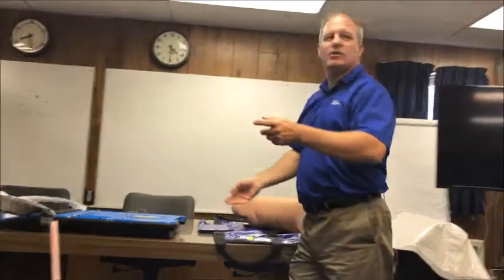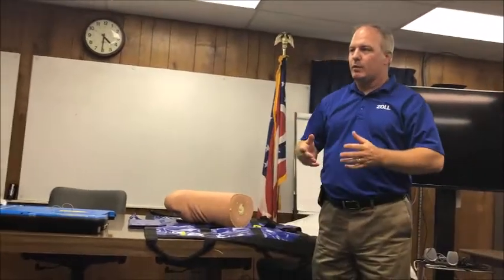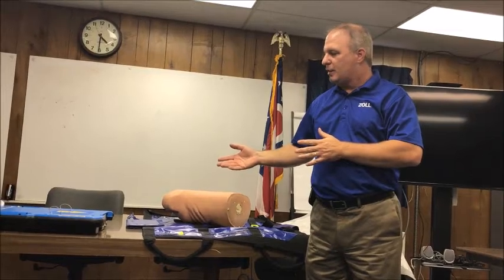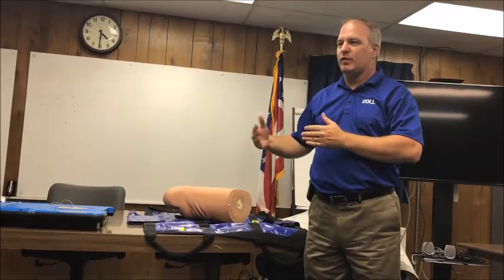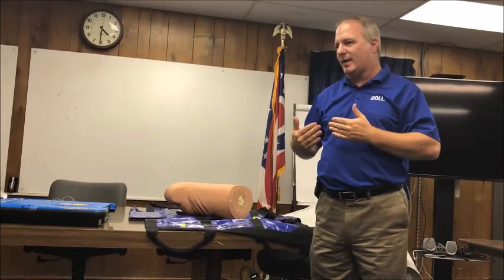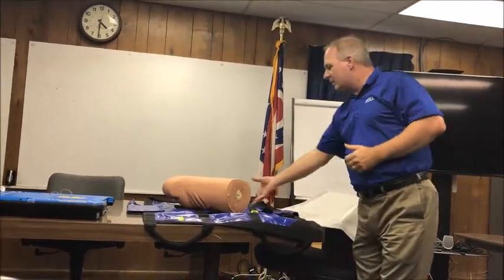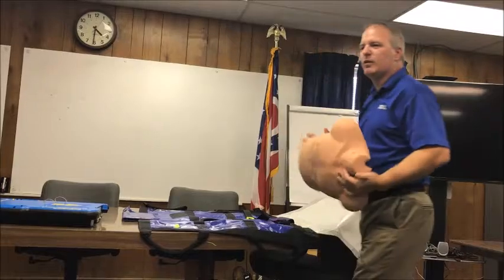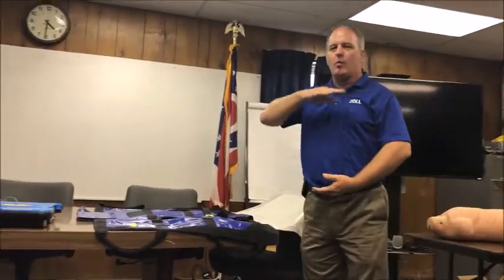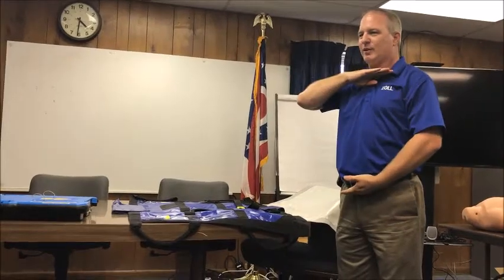Now, you had specifically mentioned backboard. Yeah. So there are devices that do mechanical CPR in the market that are a lot lighter than the AutoPulse and smaller. The thing is, they all need to have a backboard. The patient's got to be laying flat. Sure. So where this comes into play is the AutoPulse doesn't necessarily need a backboard. The patient does not have to lay flat. All we need straight is the torso. And unless your patient's got a lot of rib fractures and a spinal fracture, or they got hinges in the middle of the chest, the torso is always going to lay flat.